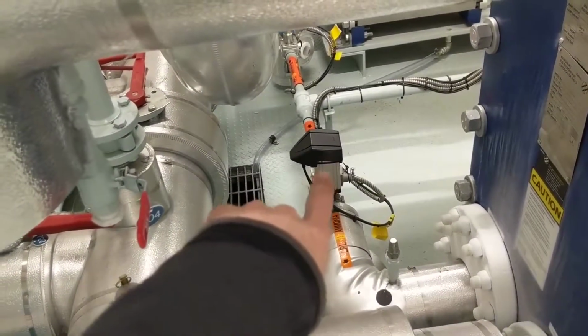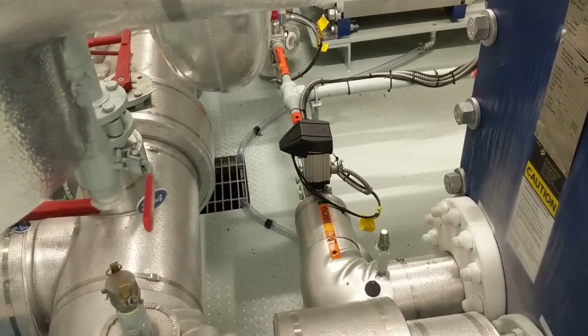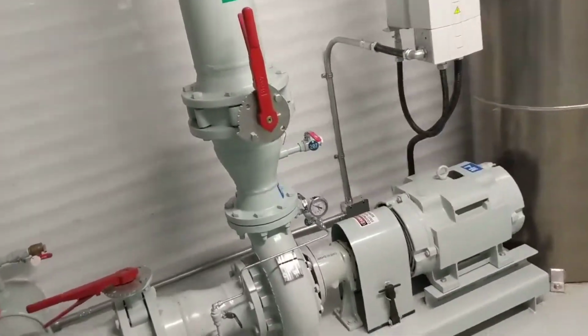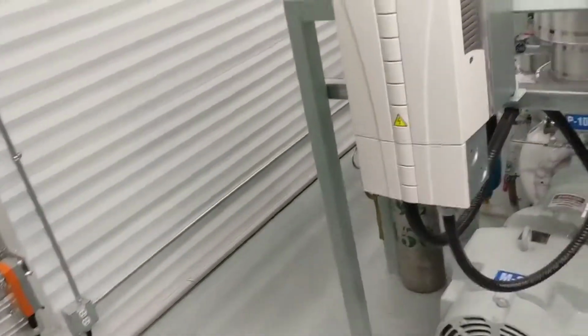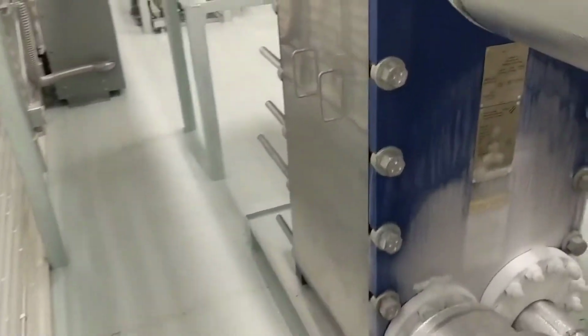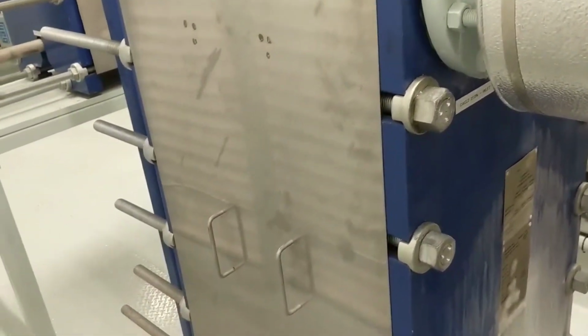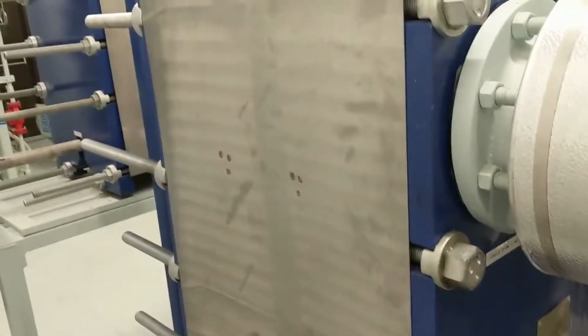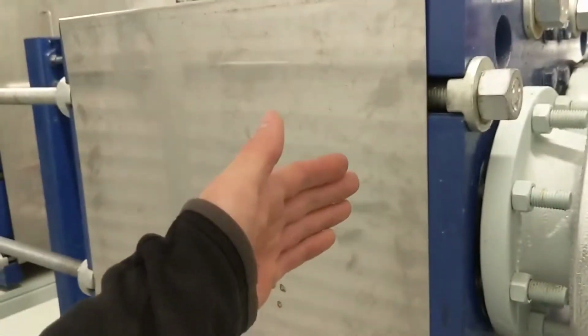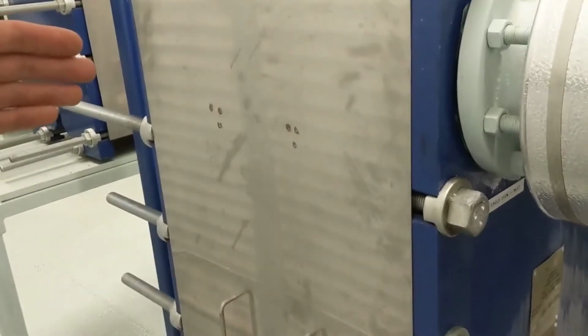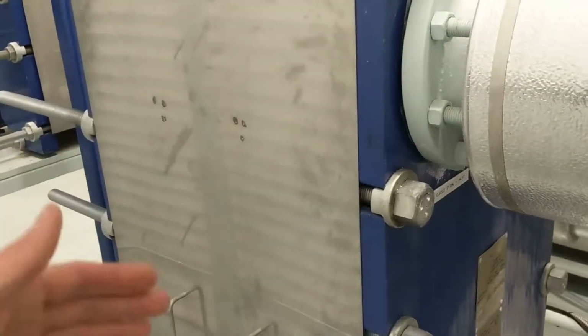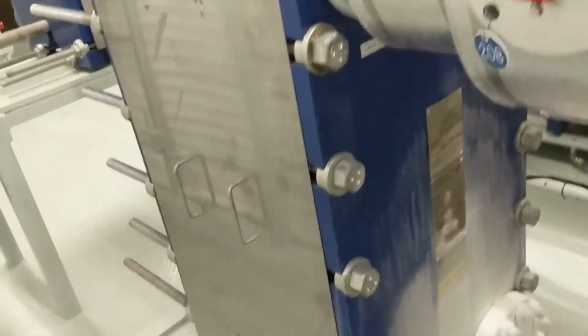Those are the electronically controlled expansion valves. Those valves modulate how much ammonia is going into the plate and frame heat exchangers, and that allows them to create the most efficient amount of refrigeration possible. These heat exchangers have got a whole series of plates in them, in which ammonia and brine flow through the alternating plates for a very efficient heat transfer.